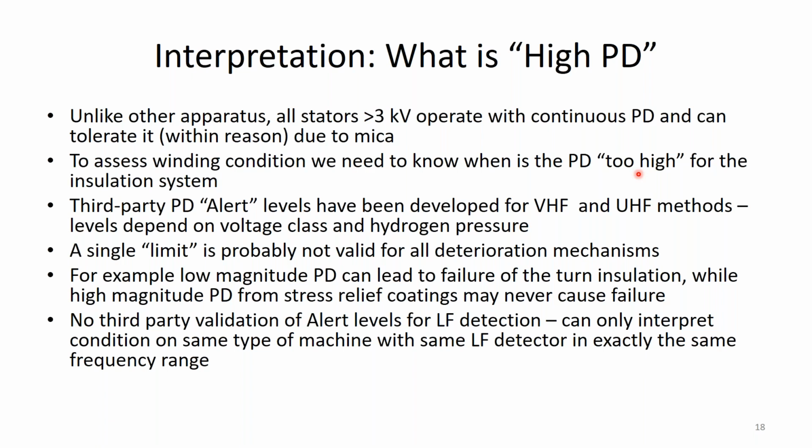Okay, so now what I'd like to talk about is a little bit of interpretation, not only how we are doing that interpretation these days, but some of the limitations of that interpretation, okay? Because when you have stuff installed in 18,000 machines, you'll learn a thing or two, especially when you're someone like me who's used to crawling around windings and finding what the real issues are. It's still the best way of determining the condition of the winding is to do a really careful visual inspection by someone who's been doing that for most of their career, okay?